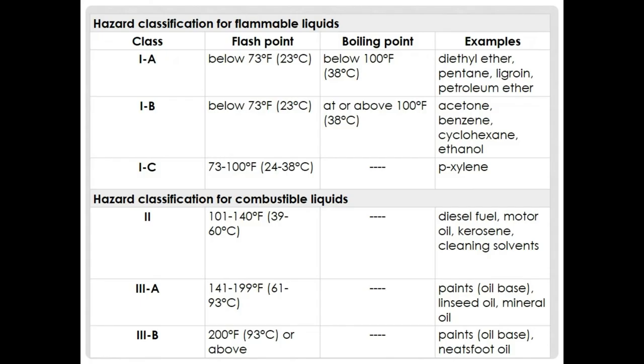Flammable liquids are divided into classes: Class 1A, Class 1B, and Class 1C, based on flash point and boiling point. Class 1A has a flash point below 23°C and boiling point below 38°C — examples include Diethyl Ether, Pentane, Ligroin, and Petroleum. Class 1B has a flash point below 23°C and boiling point above 38°C — examples include Acetone and Benzene. Class 1C has a flash point between 23–38°C — example: P-Xylene.